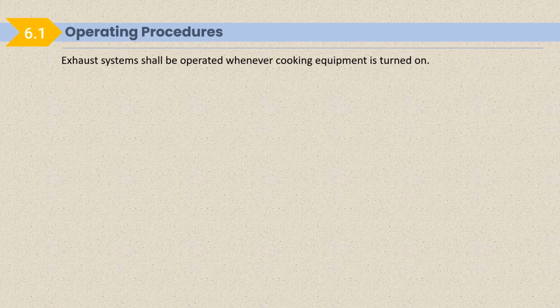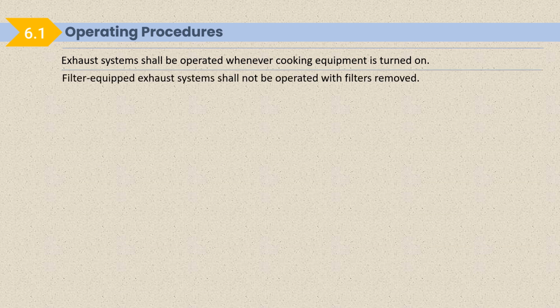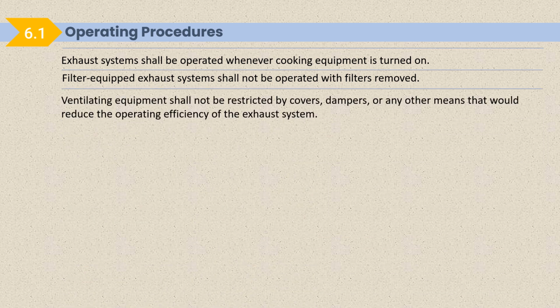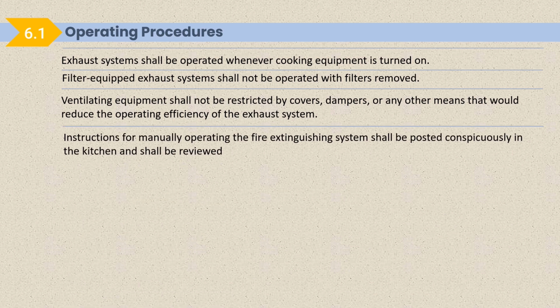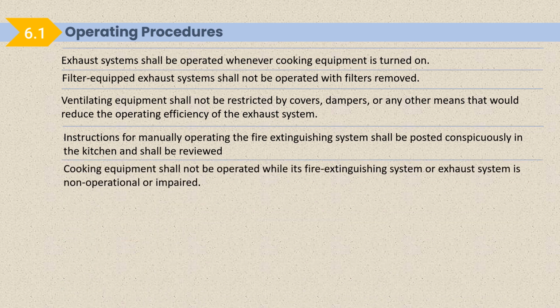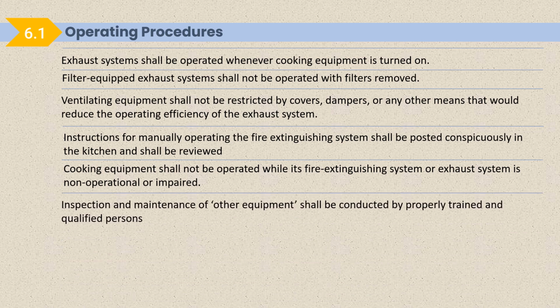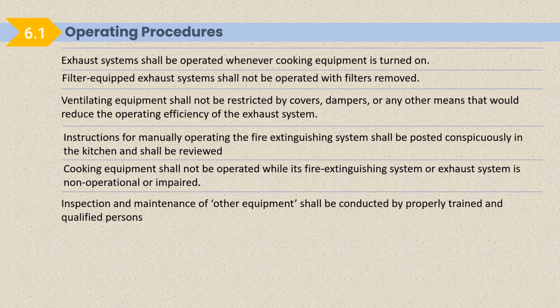Exhaust system shall be operated whenever cooking equipment is turned on. Filter equipped exhaust system shall not be operated with filter removed. Ventilating equipment shall not be restricted by cover, damper or any other means that would reduce the operating efficiency of the exhaust system. Instructions for manually operating the fire extinguishing system shall be posted conspicuously in the kitchen and shall be reviewed. Cooking equipment shall not be operated while its fire extinguishing system or exhaust system is non-operational or impaired. Inspection and maintenance of other equipment shall be conducted by a properly trained and qualified person.